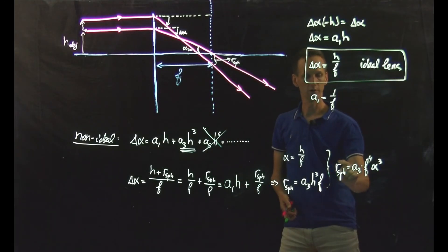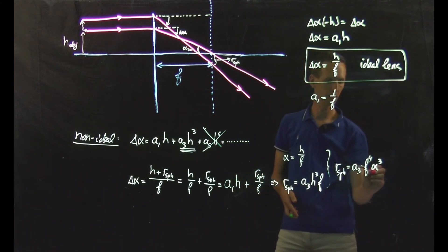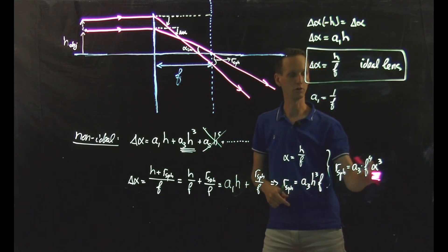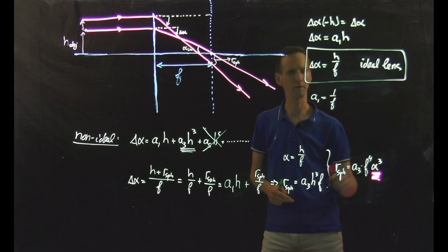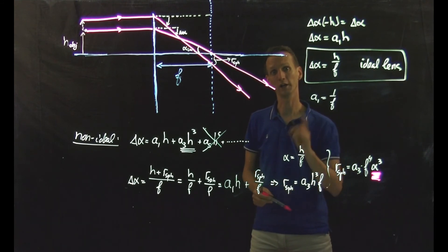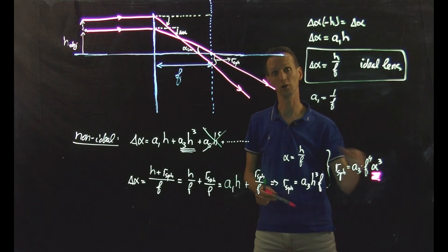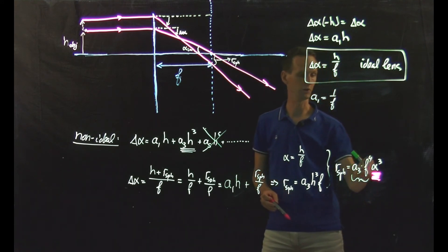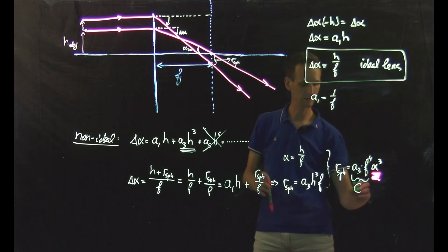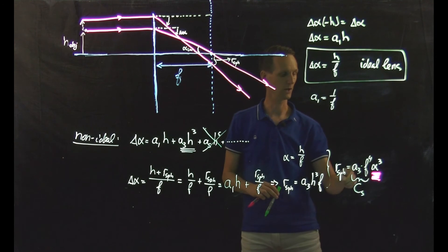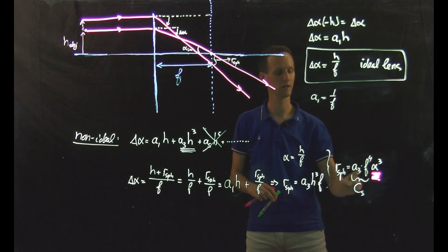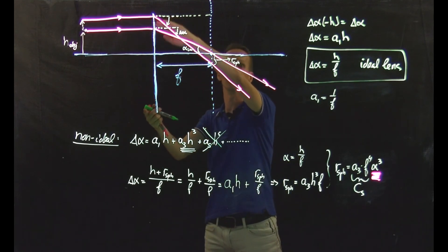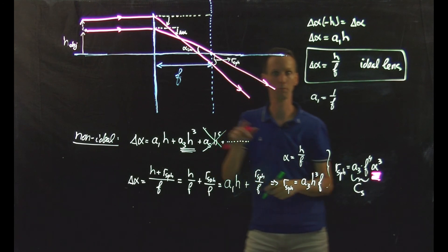The radius of spherical aberration — the blur in the focus — depends as the power 3 on the opening angle of the ideal beam. So the larger the opening angle, the spherical aberration will increase with a factor cubed. This is actually one of the reasons why in an electron microscopy system we always have a very small opening angle, as we will see in later lectures. The term a3 times the focal distance to the power 4 is a property of the lens. A stronger focusing lens has higher spherical aberration, corresponding to the fact that a stronger focusing lens has a higher curvature, leading to more deviation from the deflection for more off-axis rays.